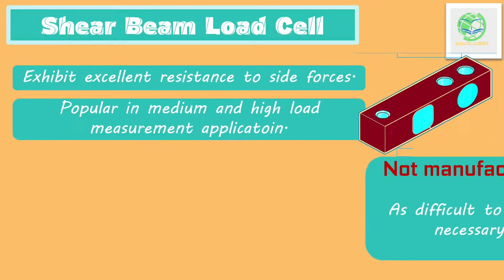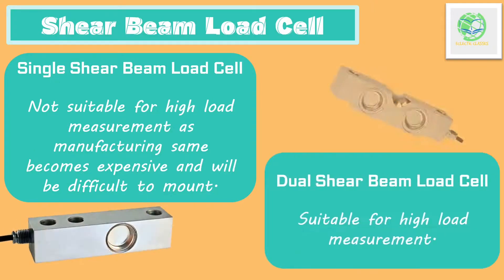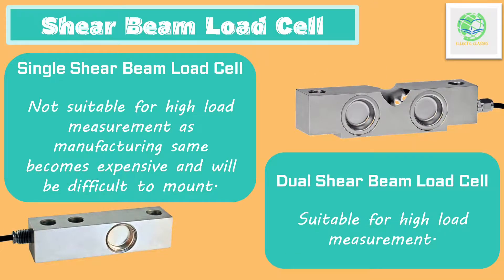These load cells exhibit excellent resistance to side forces, and shear beam load cells have become quite popular for medium and high load measurement. They are not manufactured for low load measurement, as it is difficult to make a sufficiently thin web to obtain the necessary strain levels for low capacity loads. A single shear beam load cell is expensive and difficult to mount for high capacity measurement, which is why high capacity load cells are usually based on dual shear webs in a beam configuration.